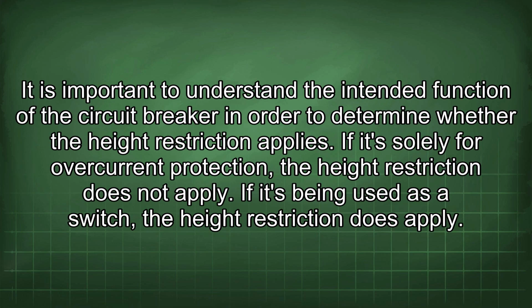It is important to understand the intended function of the circuit breaker in order to determine whether the height restriction applies. If it's solely for overcurrent protection, the height restriction does not apply. If it's being used as a switch, the height restriction does apply.